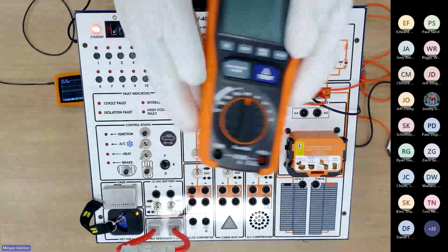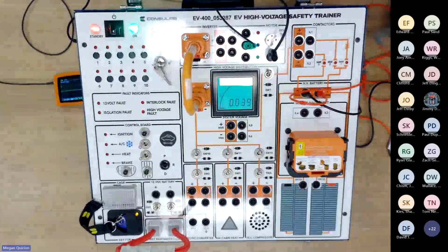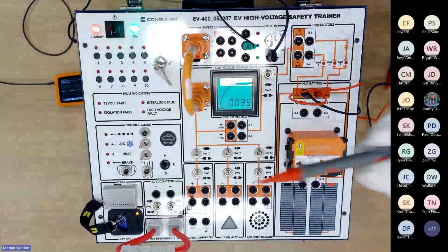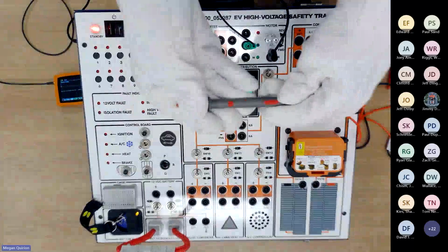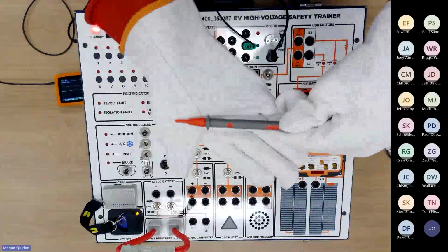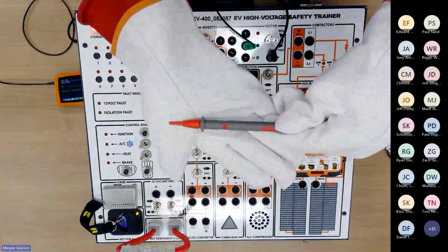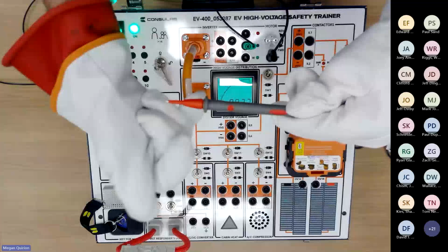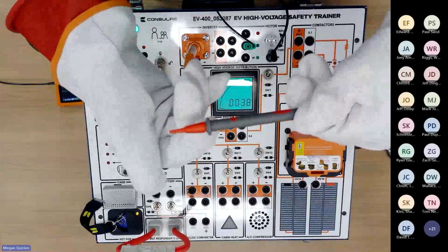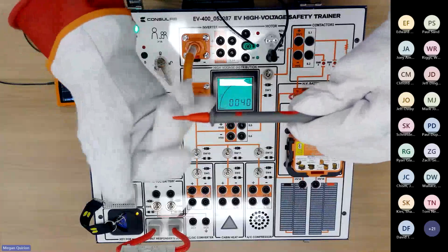But more importantly, even when you get a meter that's Cat rated, you want to make sure the components you're using with the meter are also protected. So the Cat rating on a meter lead is very important too, ensuring the meter has the proper leads when testing.